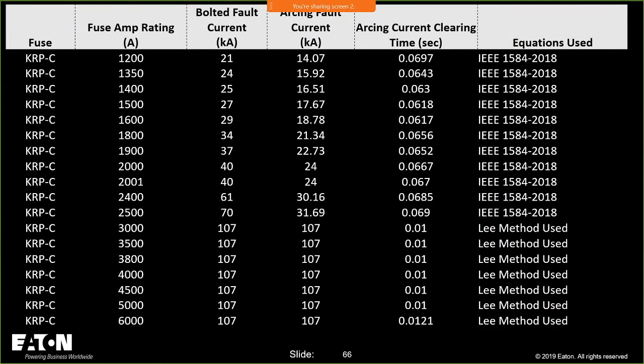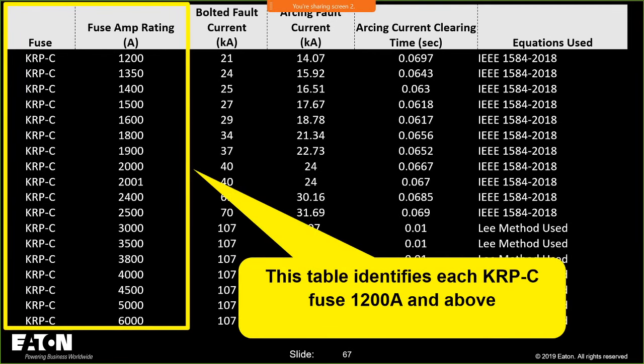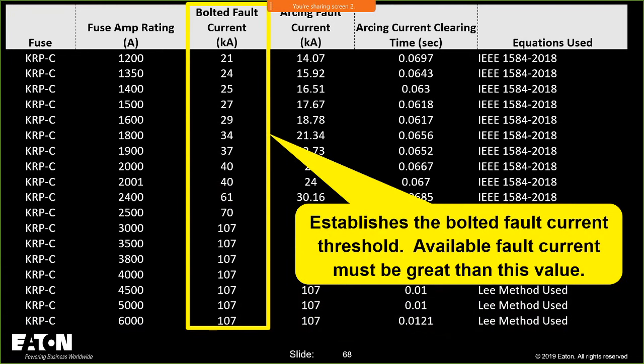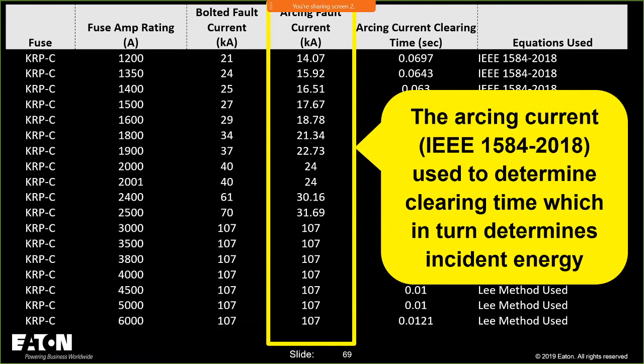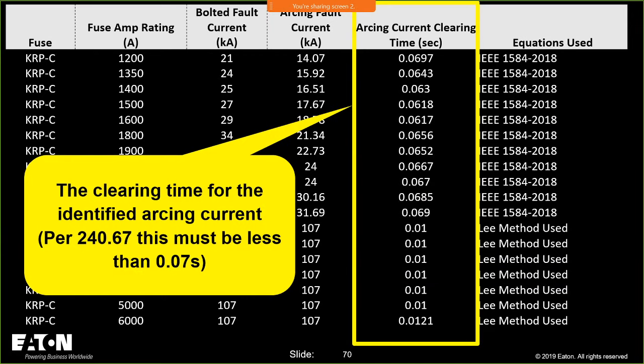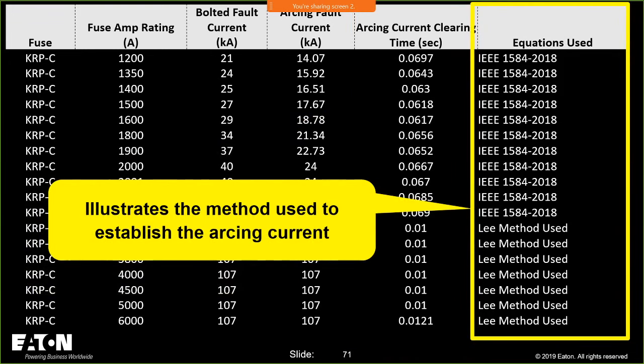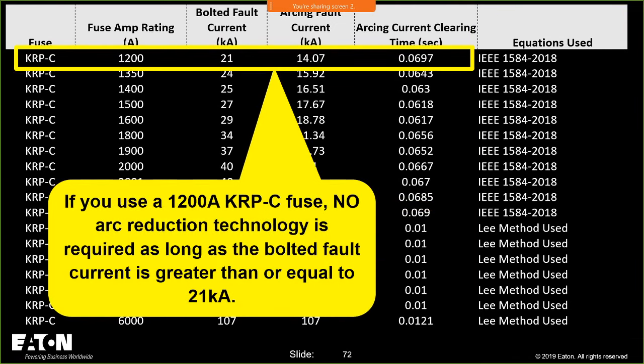This is just a table format. I'm not going to walk through this because I basically already did that. This is just the raw data that I used to generate that screen. So I'll just arrow through these so that if you're watching it on YouTube, you can pause the video and take a look at it. I'm showing the arcing currents, the bolted fault currents, and the actual clearing times that SKM put out for me. And I'm showing you, obviously, where the Lee method for a 480 volt system takes over. So I can say that if I have a 1200 amp KRPC fuse, no arc reduction technology is required as long as the bolted fault current is greater than 21,000 amps.